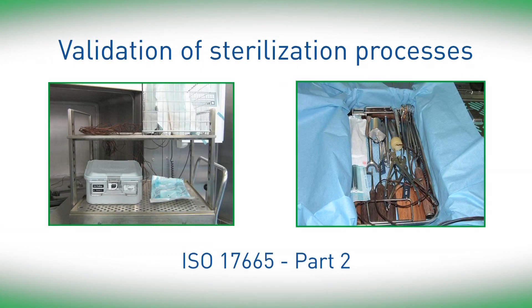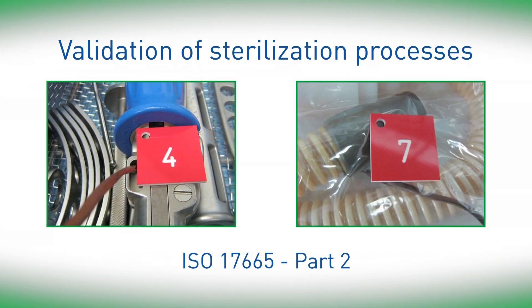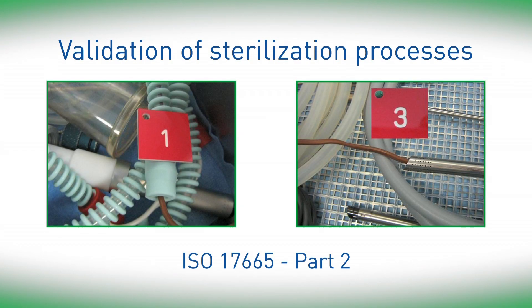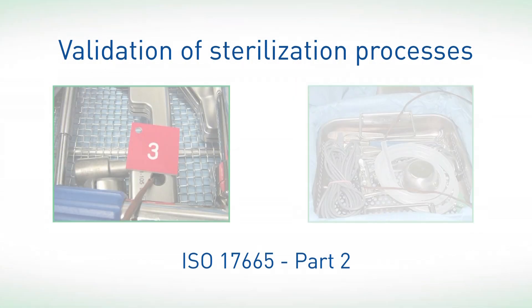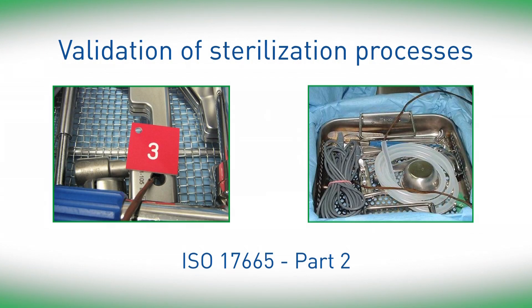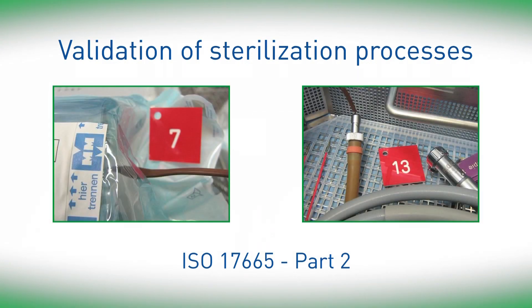In order to ensure that every sterilization process leads to a demonstrably successful sterilization, the process is subjected to a validation. In this situation, proof is provided that the process can be reproduced — that is, that the parameters required are maintained for every batch, provided that the operator maintains the conditions determined for the validation.